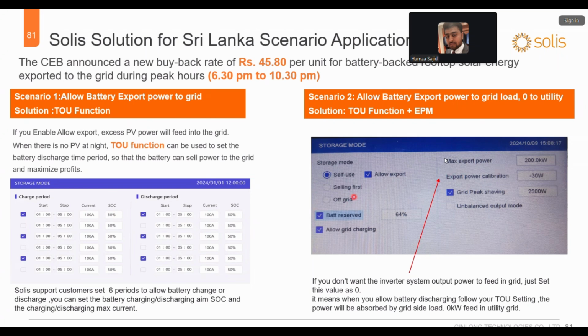Another thing, there was a question from one of our guests: how can we set the maximum export power? You can see over here, when you allow export power to grid, you can easily set how much power you want to export back to grid. In cases where grid voltages get higher, you can easily set the maximum power back to grid. And you can also use the grid peak shaving functions if required. And one more thing for the three-phase inverter is unbalanced output mode.